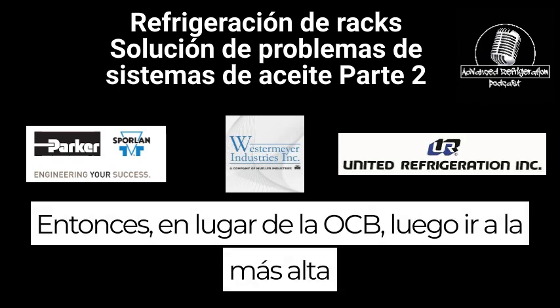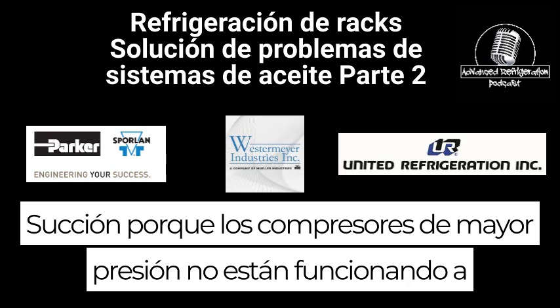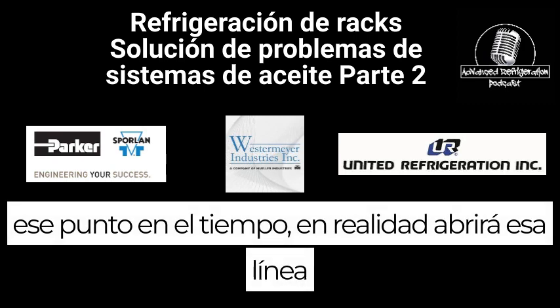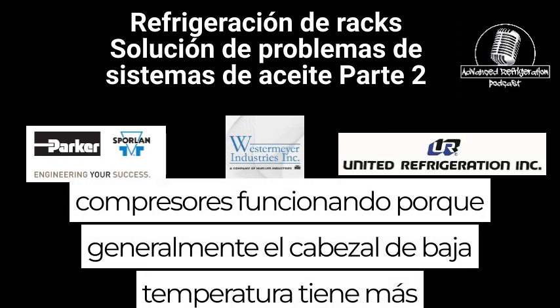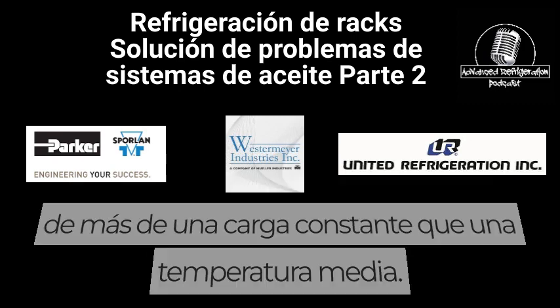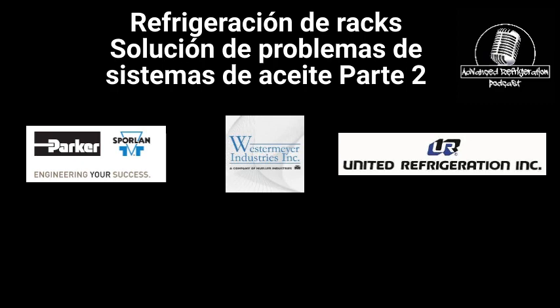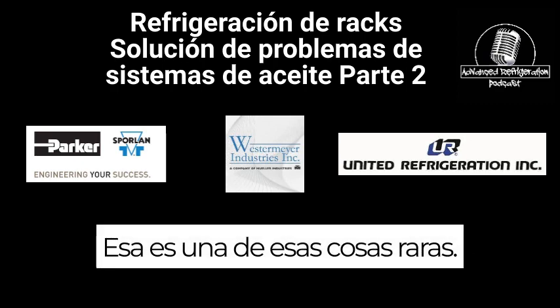So instead of the OCV going to the highest suction, because the highest pressure compressors are not running at that point in time, it'll actually open up that line to the low temp and keep the low temp compressors running, because usually the low temp header has more of a constant load than a medium temp. Yeah, I agree. That's not a thing you see very often. It's one of those oddball things.